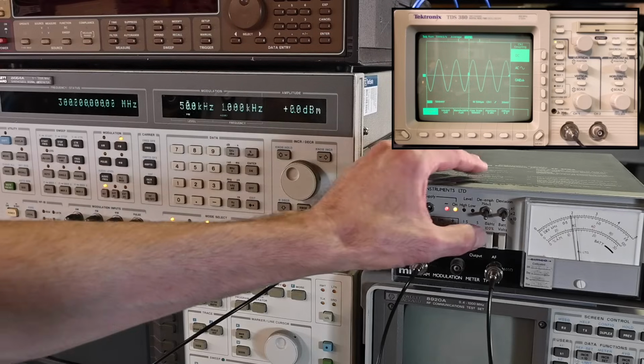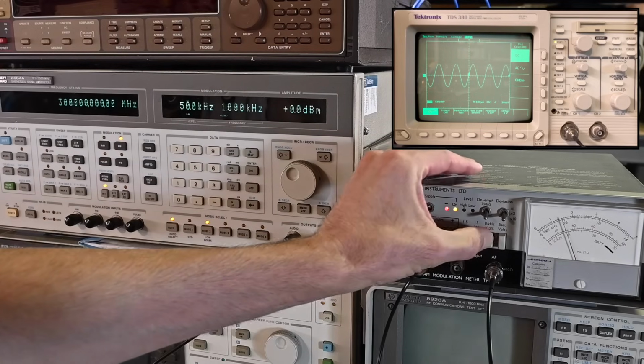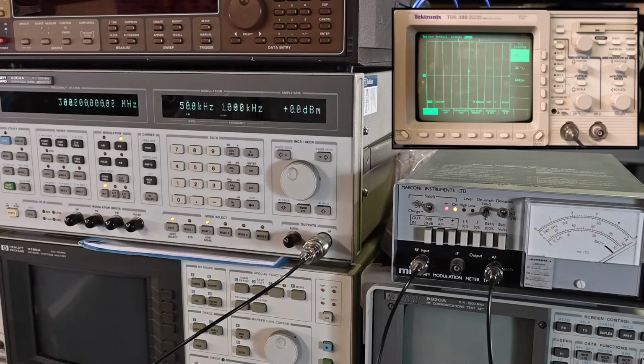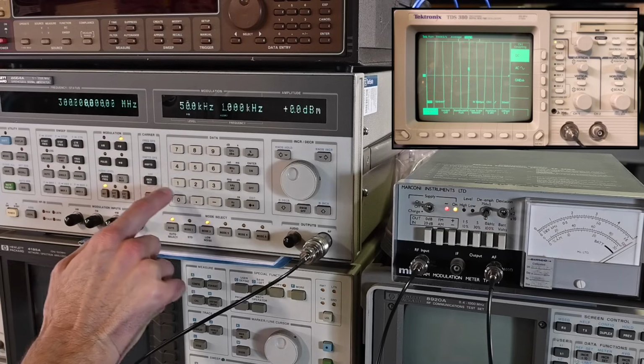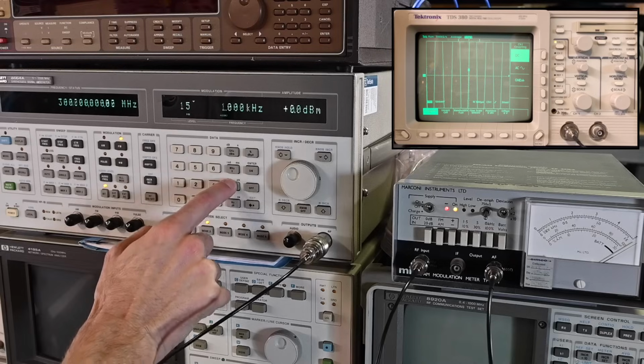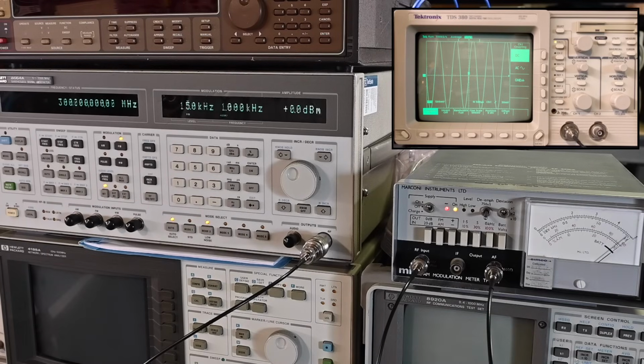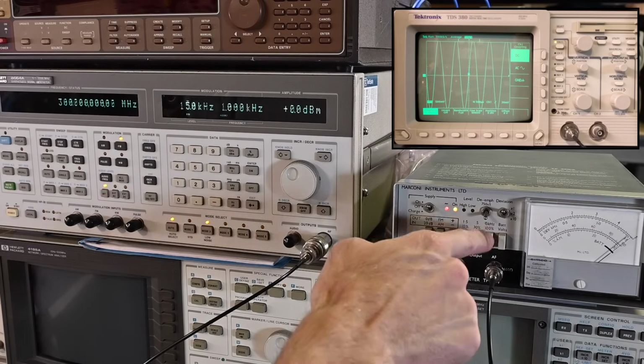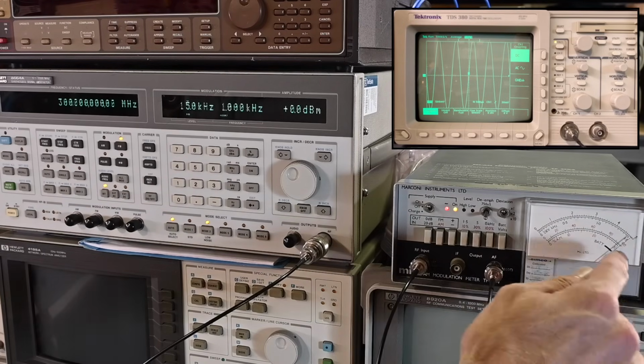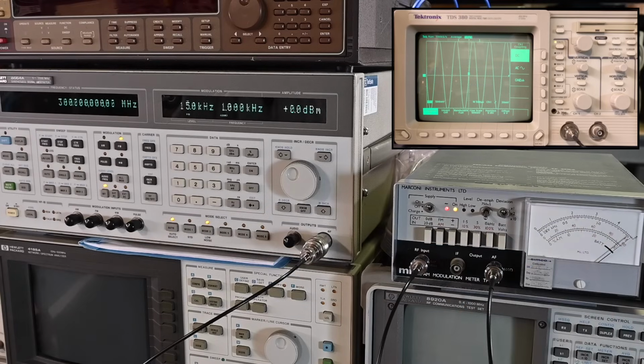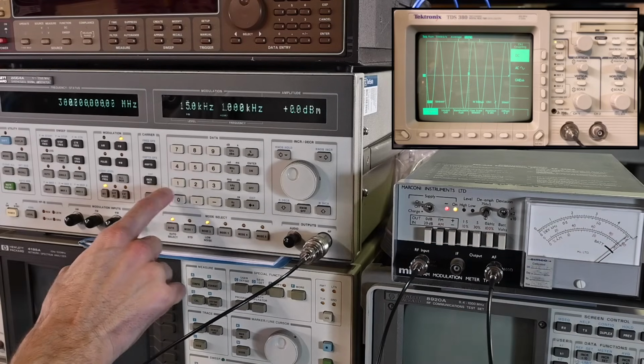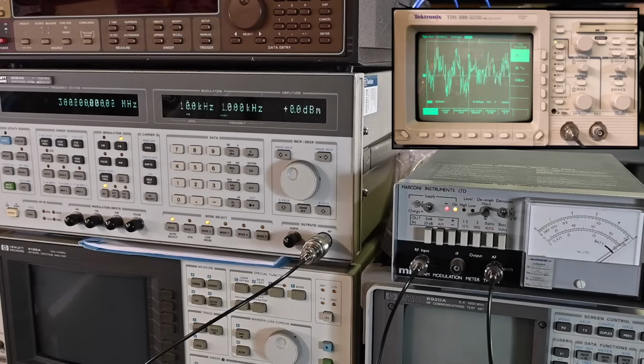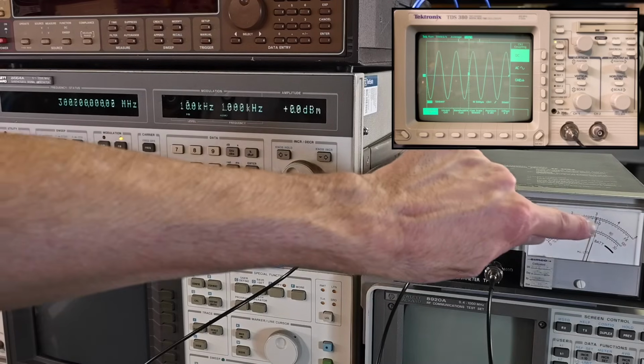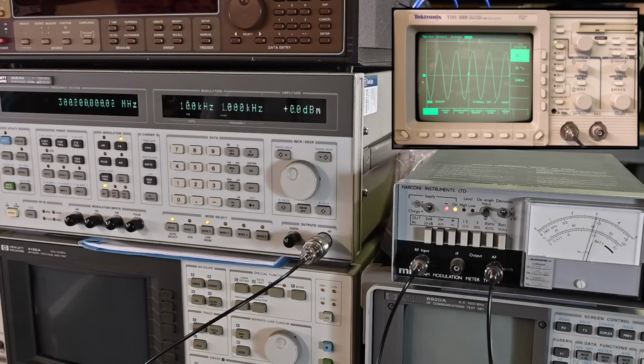So now if I go to 15 kilohertz, put this back up to times 1, FM 15 kilohertz, and yes, that is full scale. Now on 15 kilohertz we're reading one scale down, so the 1.5 becomes 15. If I back that down a little, say to 10 kilohertz, you can see it's on the 1.0, but that's read as 10 now. So no problems there, that's fine. That range is working the way it's supposed to.